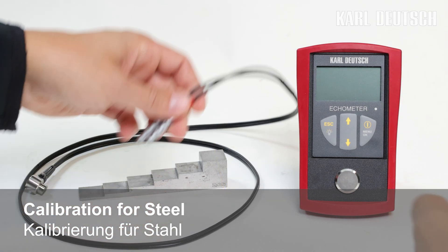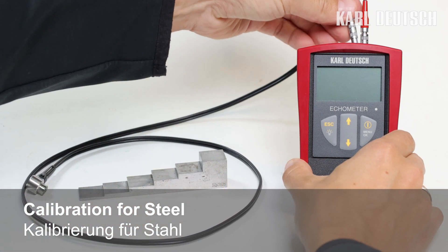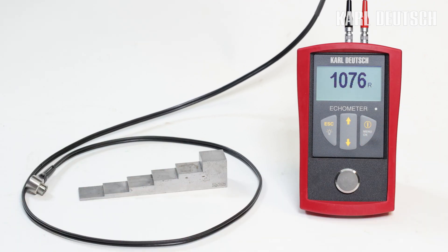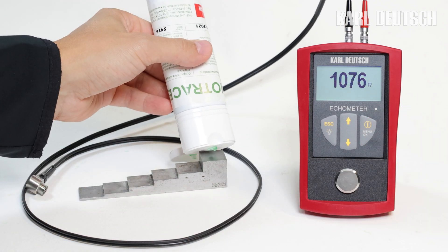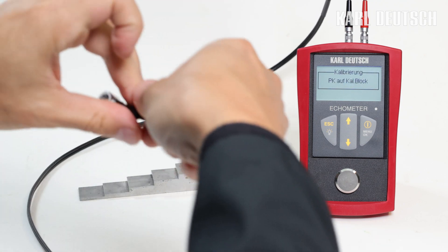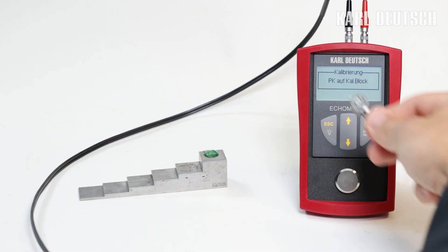Measuring wall thickness with an ECHOMETER is simple. The device is switched on and the probe is connected. Now the probe is placed on the calibration plate integrated into the instrument with a little coupling agent and will be automatically adjusted.